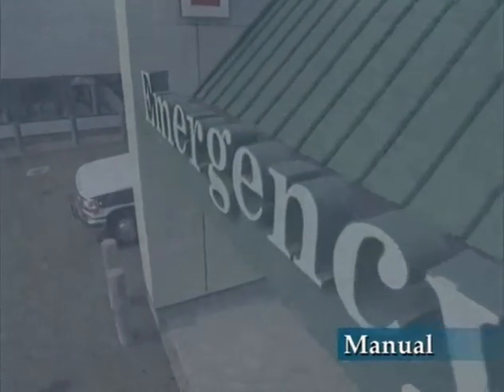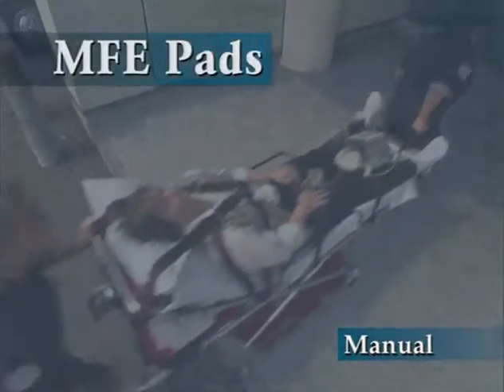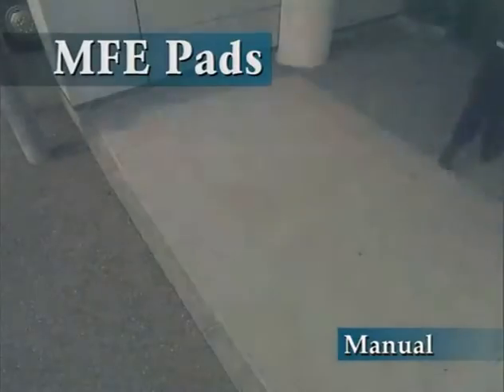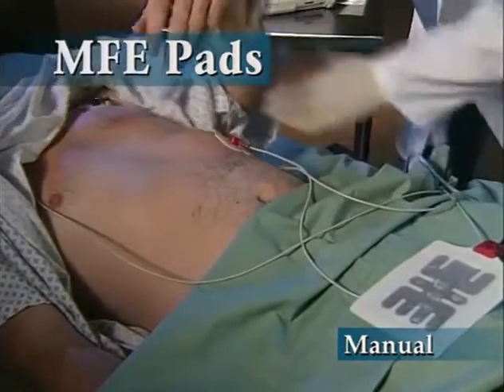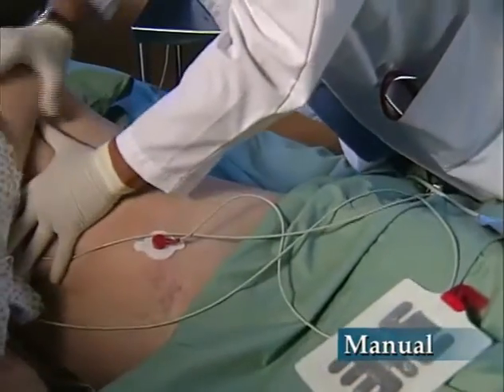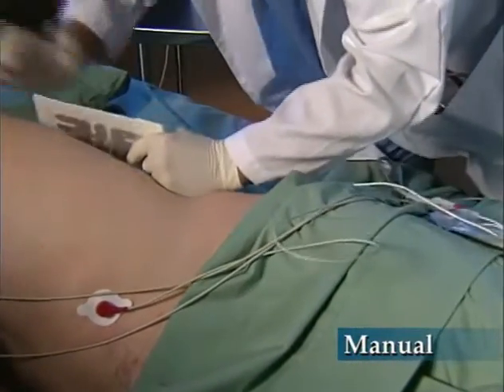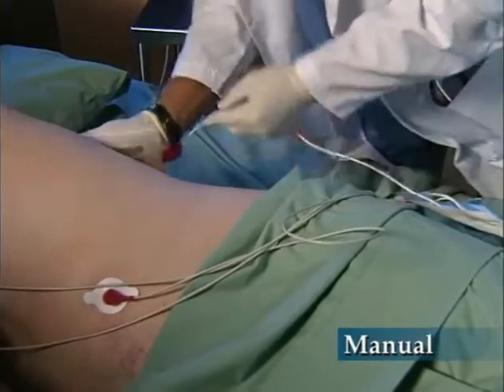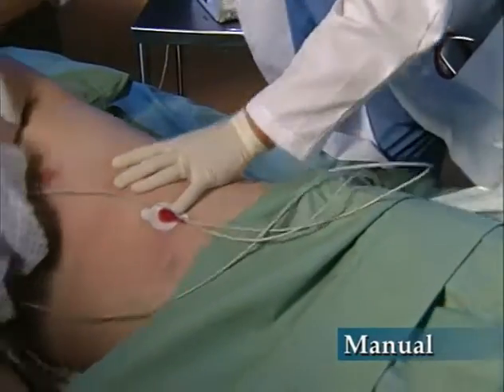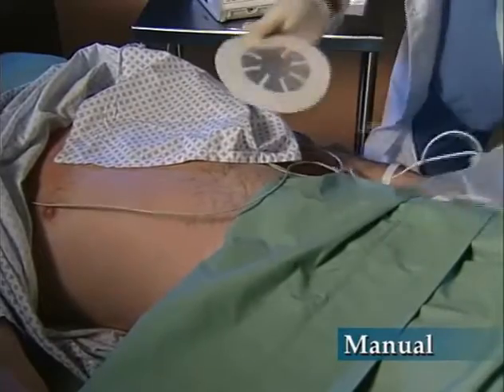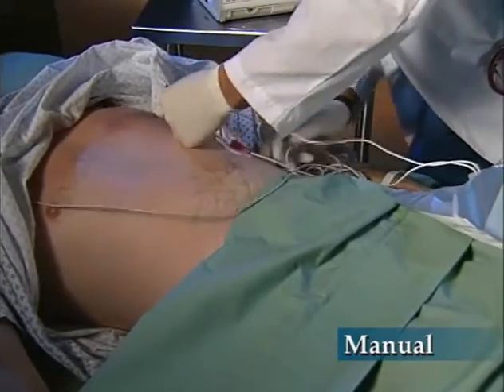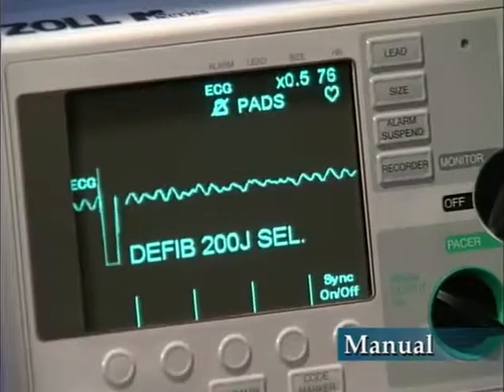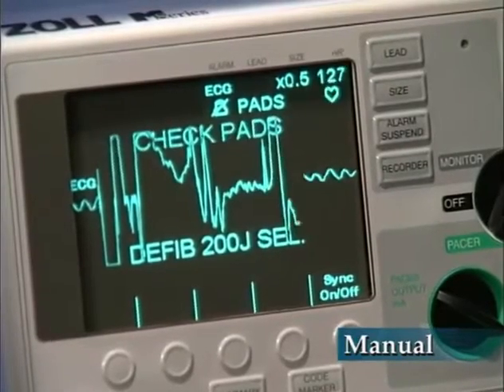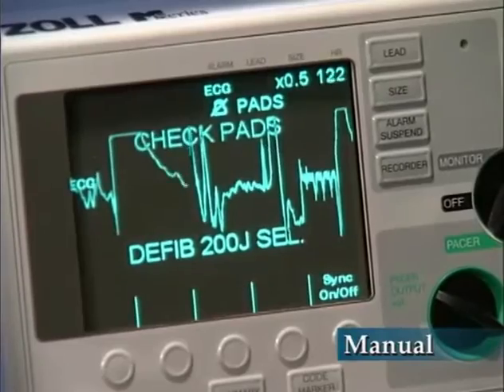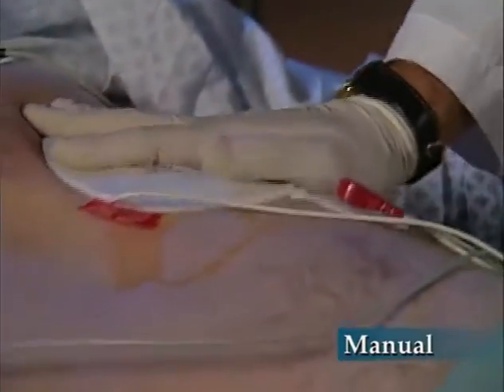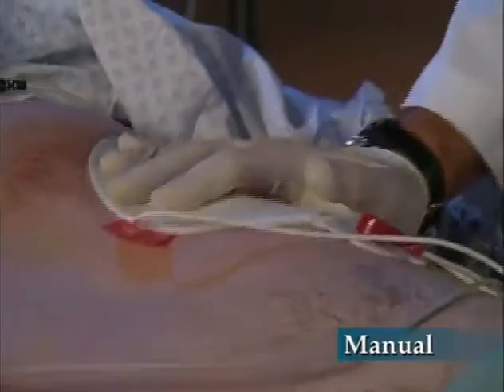The procedure for using multifunction electrode pads in manual mode is similar to that used with paddles. Attach the multifunction electrode pads to the patient according to the directions on the electrode packaging. Ensure that the multifunction electrode pads make good contact with the patient's skin and that they are not covering any part of the ECG electrodes. If the multifunction electrode pads are not making good contact, the messages "check pads" and "poor pad contact" will be displayed alternately and energy will not be delivered. Pressing the pads down can correct this problem.